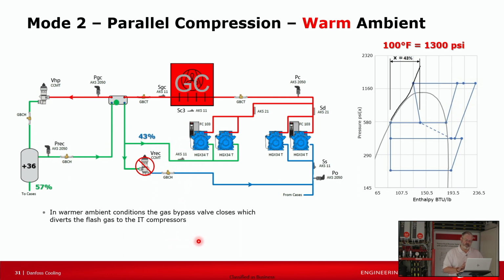So now instead of going to your medium temp suction, you'll see that path winds up at the parallel compressor suction inlet. So at that point, we had 57% of our mass flow is liquid. That went out and served our cases. That still needs to return to the medium temp suction. However, 43% of our overall mass flow was able to go to our parallel compressors.